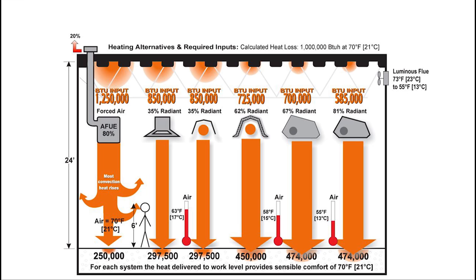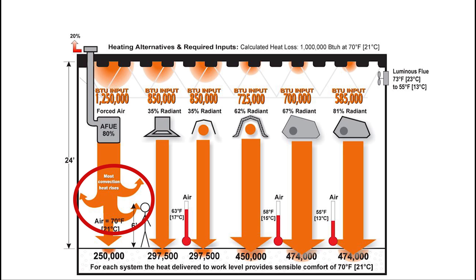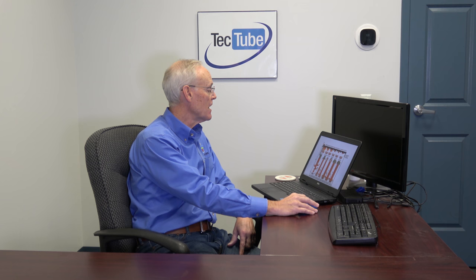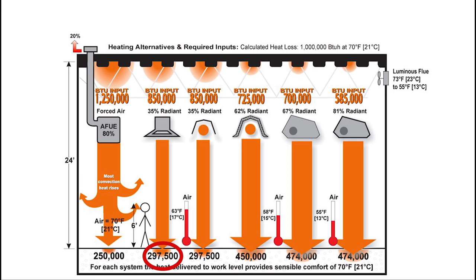You can see a standard unit here with an AFUE of 80 to 82 percent. If I have a calculated heat loss of one million BTUs, because of that 80 percent efficiency we have to use inputs of 1,250,000 BTUs — and you can see that a lot of the heat is going up toward the ceiling. To get 250,000 BTUs down to the floor level at an ambient temperature of 70 degrees, you need inputs of 1,250,000. With the industry standard of 35 percent radiant on high intensity, you can reduce that load by 15 percent, so you're only selecting an input of 850,000 — and you get quite a bit more heat down at the floor level.